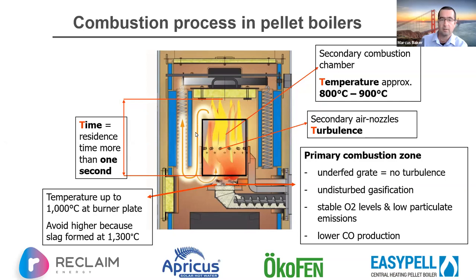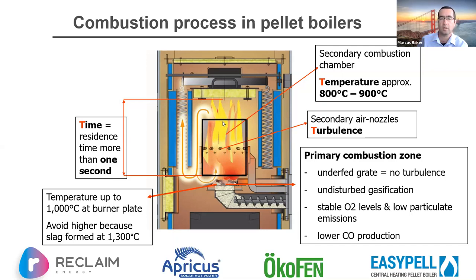The flue gases are forced back down, so you get quite a bit of heat transfer into the water jacket at this point, and continued high-temperature performance. Heavier particles — meaning those with more combustion product remaining — tend to drop further down and get reintroduced back into the cycle, giving them another opportunity to release any extra energy.